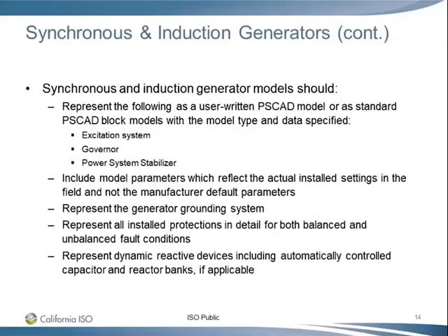So you can submit a model either in the PSCAD library using PSCAD library blocks, or you can have a user written model. Actually, in PSCAD there's a function you can use to translate the model in PSSE format into the PSCAD format, but there's no translation for PSLF model format yet, I think. But people do use that. For the PSSE, PSLF dynamic model for a single generator, the conversion is quite easy. I think you should be able to use the eTrans function to directly import the PSSE model into PSCAD, and that's probably the easiest way to handle that.